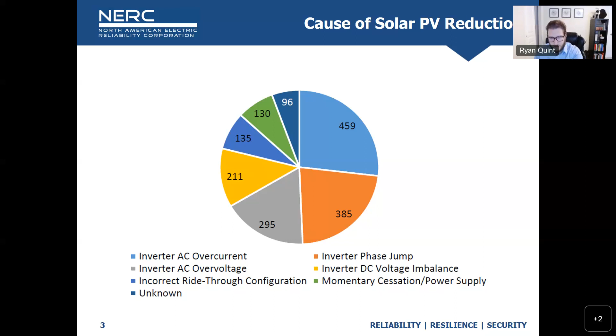The causes, which Patrick talked about on the last webinar, were inverter level AC overcurrent, inverter level phase jump tripping, which is a form of passive anti-islanding protection, inverter level instantaneous AC overvoltage protection, inverter level DC voltage imbalance, one plant with incorrect ride-through settings configured, and one plant going into momentary cessation, plus a small number of unknown causes we couldn't get answers to for various reasons.